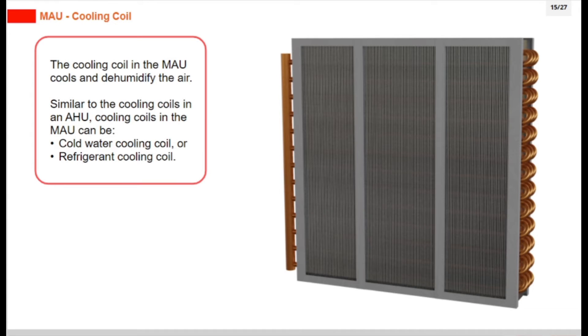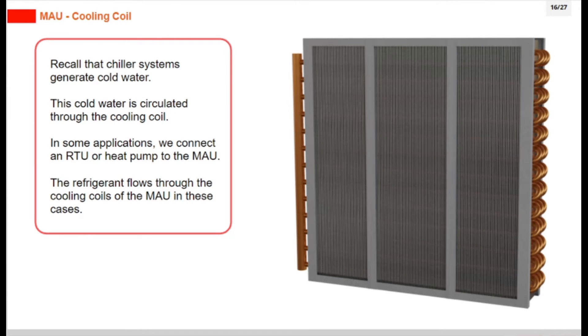The cooling coil in the MAU cools and dehumidifies the air. Similar to the cooling coils in an AHU, cooling coils in the MAU can be a cold water cooling coil or a refrigerant cooling coil. Recall that chiller systems generate cold water, which is circulated through the cooling coil. In some applications, we connect an RTU or heat pump to the MAU, and the refrigerant flows through the cooling coils in these cases.